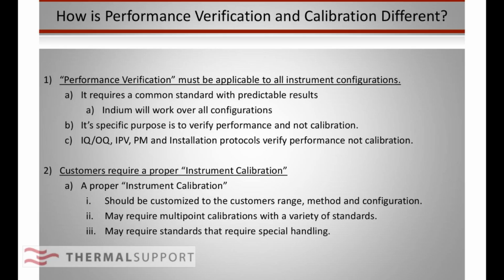Whereas if you have an instrument calibration, now you're looking at making sure the numbers work right in your particular range, maybe your particular sample pans. Is there any special handling on this? There's just a lot of variables that go in there, which you certainly want to make sure are right. But the number one thing you need to do is make sure that the instrument's performance verification is exactly what you expect it to be. Otherwise, this can be problematic.